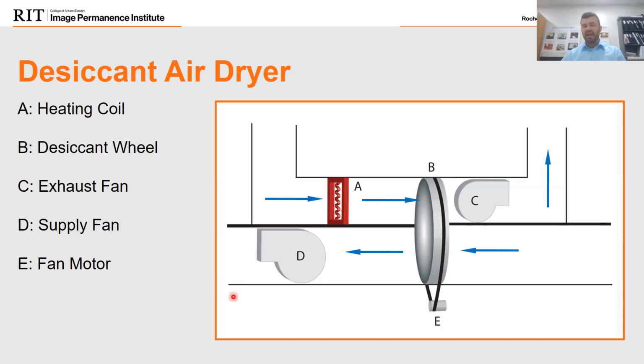So it's going to superheat that air, blow that air across the wheel, and it's going to pick up a lot of the moisture that was on the process side and then blow that air out of the building. So the top U vent duct that you see here, that's going up and out of the building entirely. So this air will come through your building, but doesn't get exhausted anywhere in your building. This is pulled from outside and exhausted outside. And the bottom duct is within your collection space or air handling unit and outside of and back to your collection space.